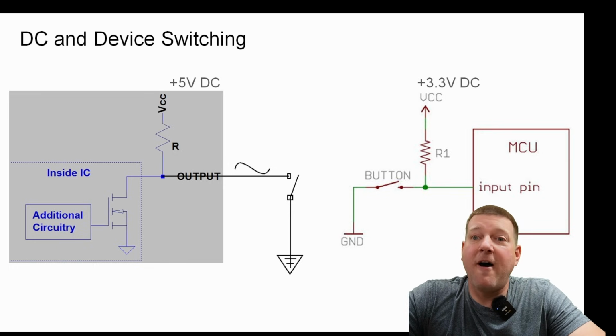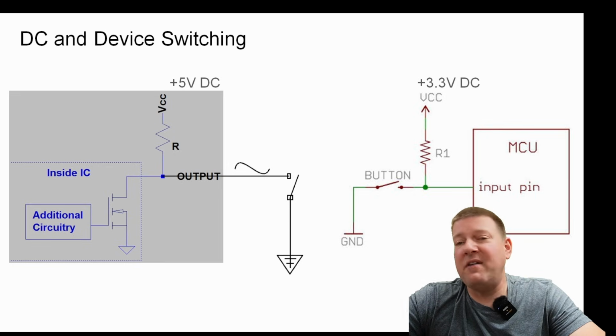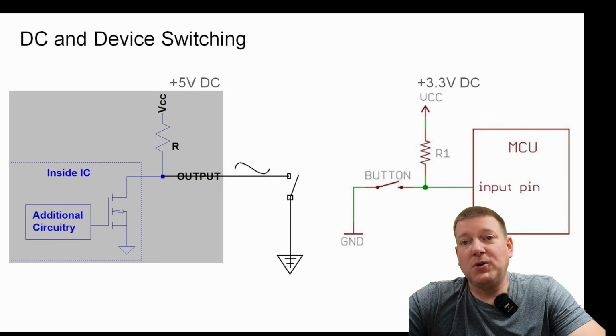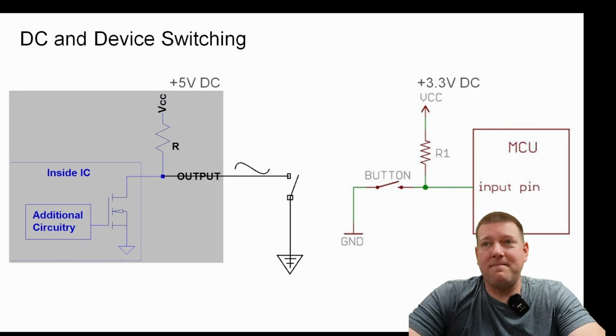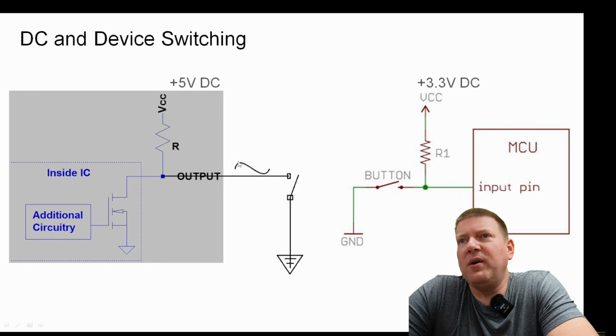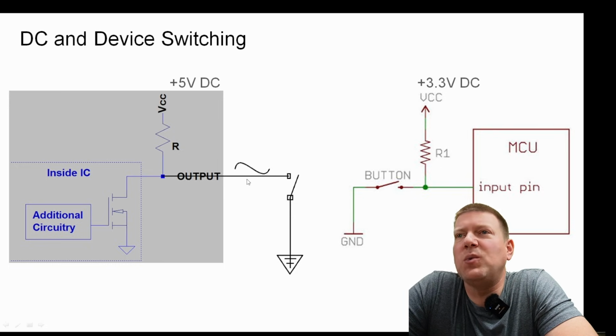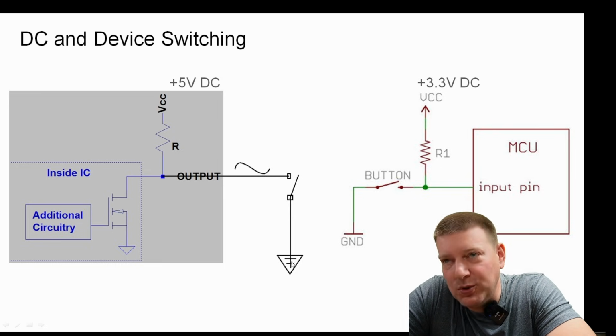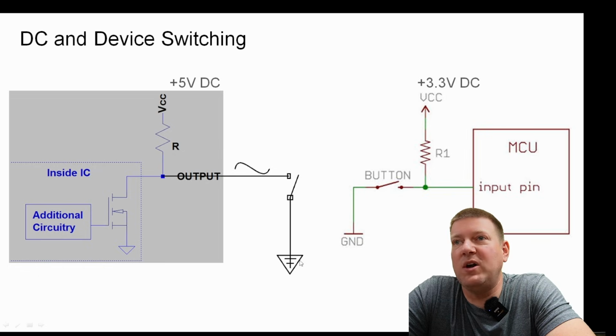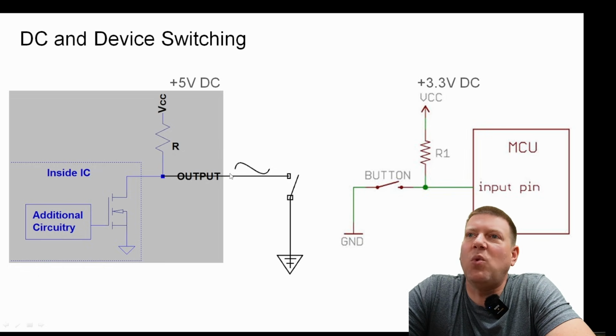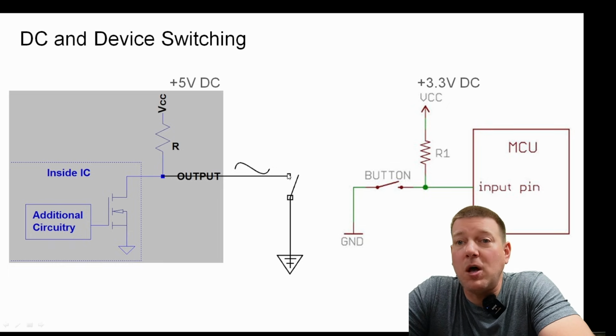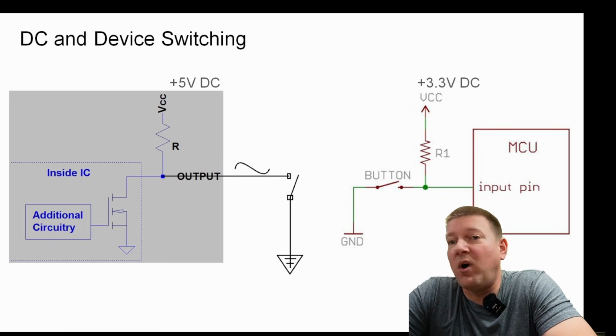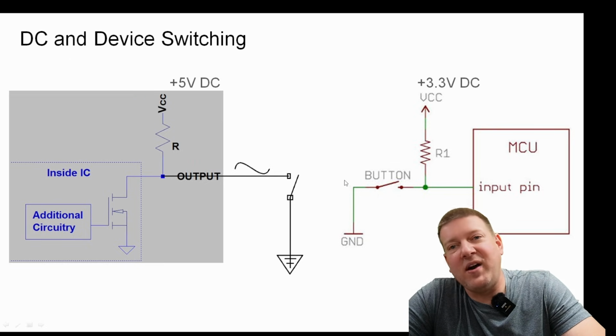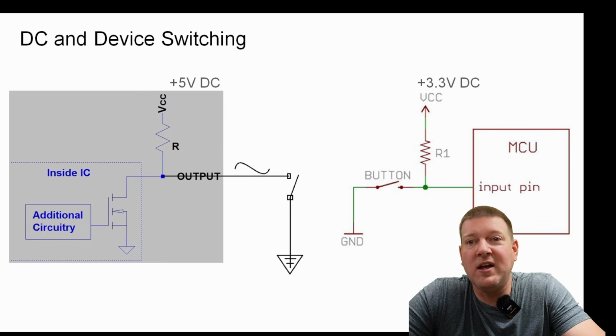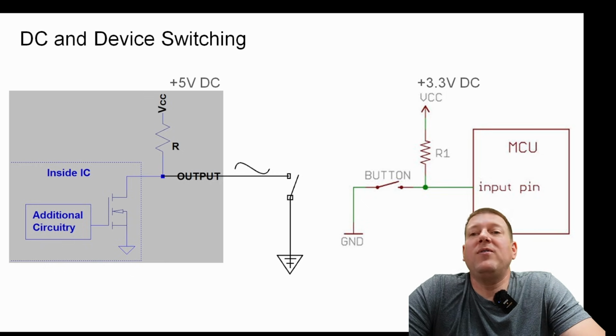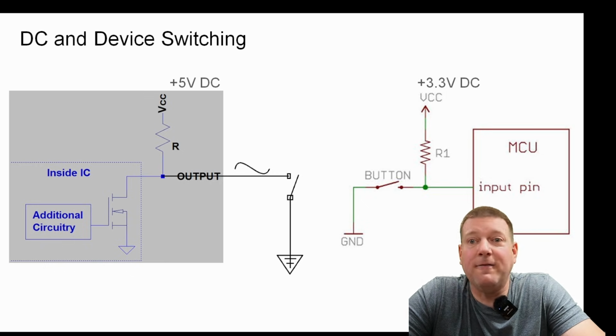However, they often have internal ones. You don't see them, you'll never see them, but you can see their physical traits. What do I mean by that? See this wire right here with this little squiggly line? I drew that squiggly line there along with this switch to ground. So you can see that one side of my switch is always grounded, and this wire up here, if the switch isn't closed, it's just open, right? It's just a wire. And what did I say earlier happens to wires if they're just sitting out there, floating, not connected to anything? They will develop a current, and they are an antenna for noise.